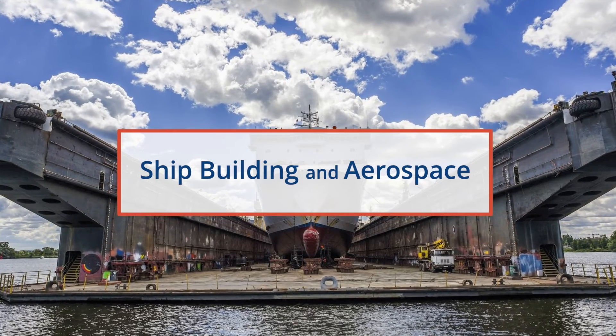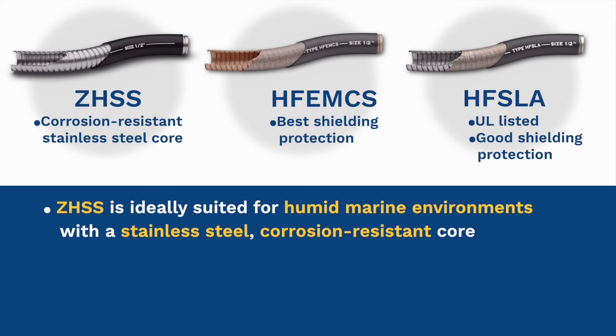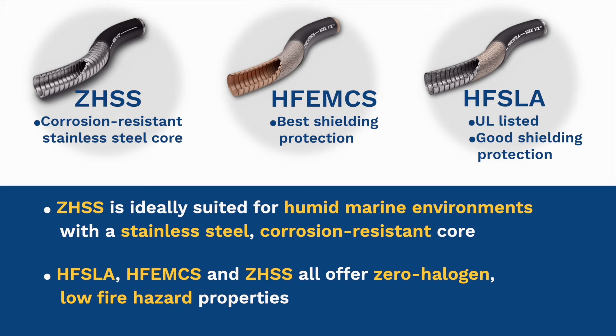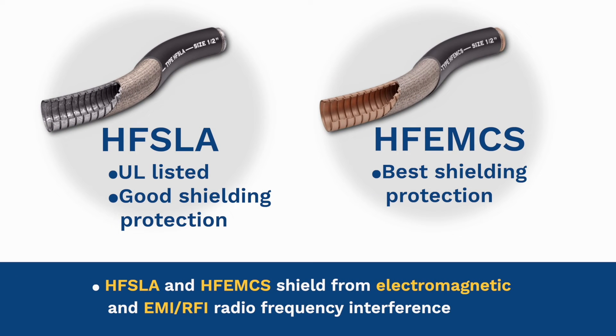For shipbuilding and aerospace applications, safety, UV resistance, shielding capabilities, and durability are critical. Conduits should be free of halogens in the event of a fire and offer flame-retardant qualities. Type ZHSS is ideally suited for humid marine environments with a stainless steel corrosion-resistant core. Types HFSLA, HFEMCS, and ZHSS all offer zero halogen, low fire hazard properties. Types HFSLA and HFEMCS shield from electromagnetic and EMI RFI radio frequency interference.